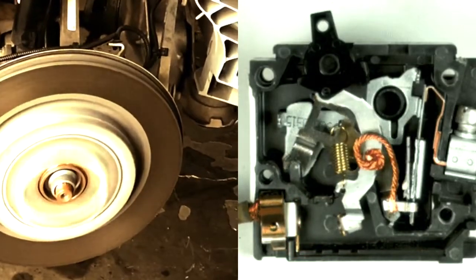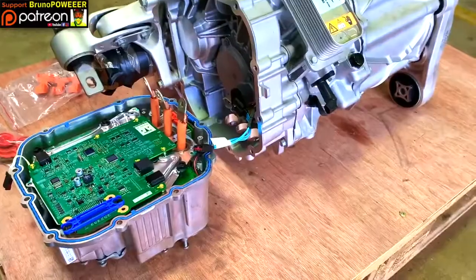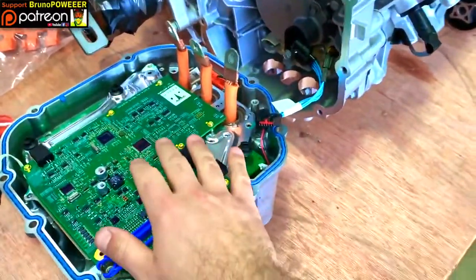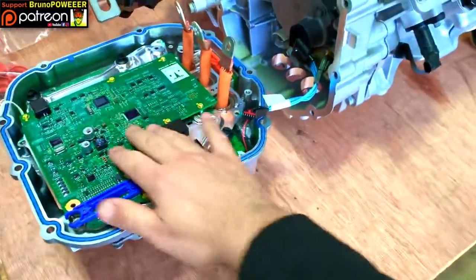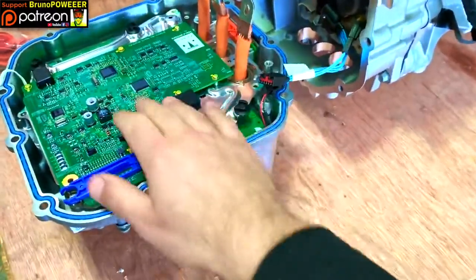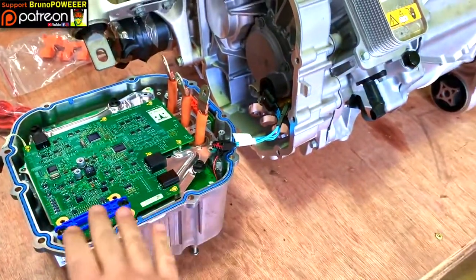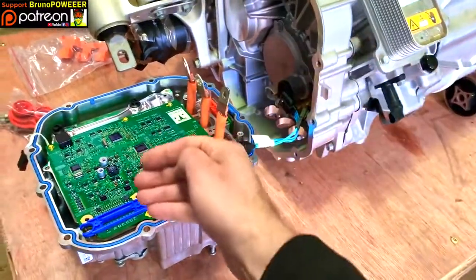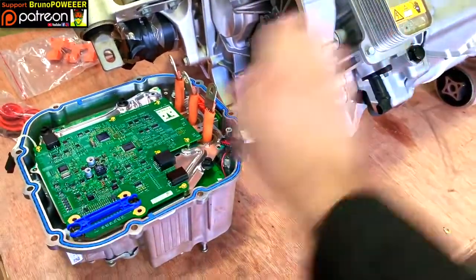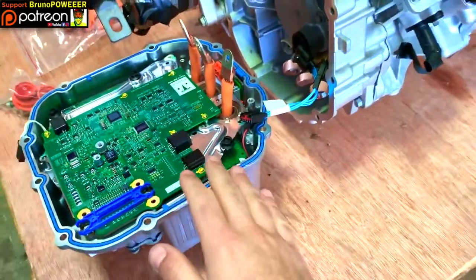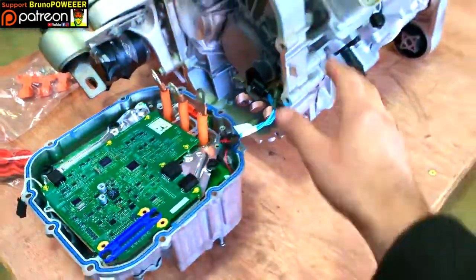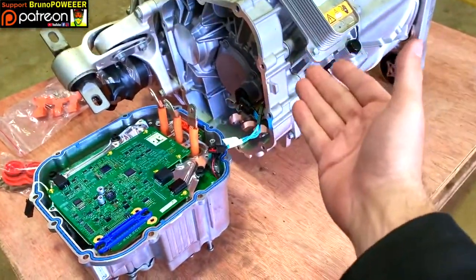And then eventually, after a lot of tests, the circuit breaker tripped. And then the logic board stopped controlling the power, because normally the logic board is actually controlling the whole power section, feeding power to the motor, regen, controlling in and out, managing the whole lot. So suddenly everything turned off and the motor was spinning at 16 or 18,000 RPM.